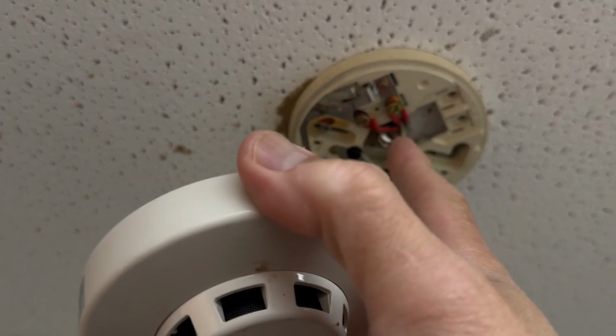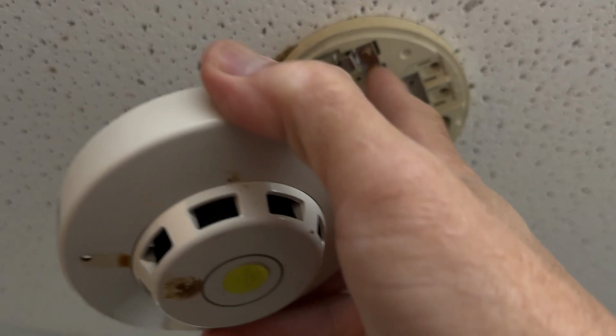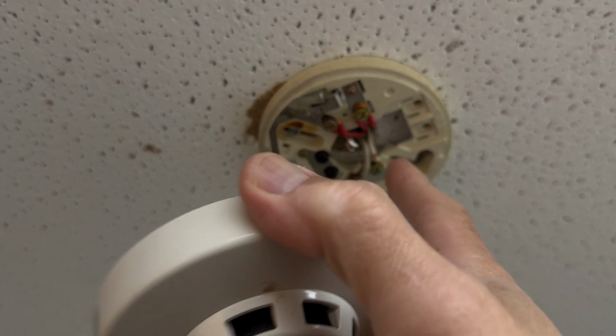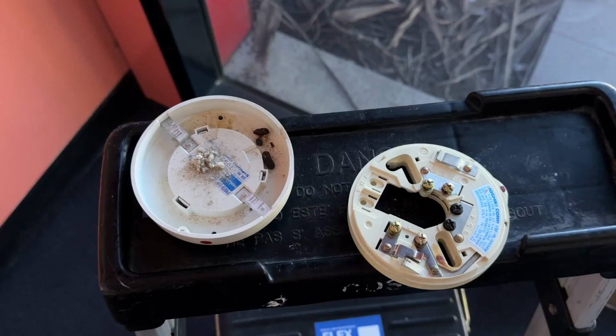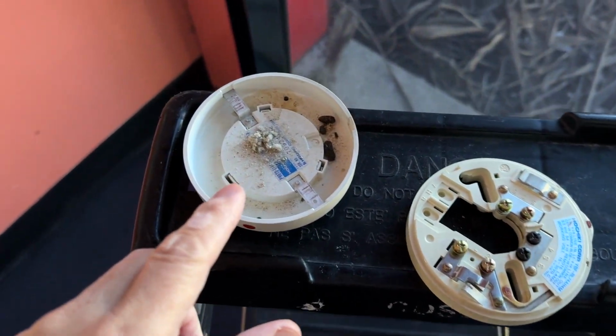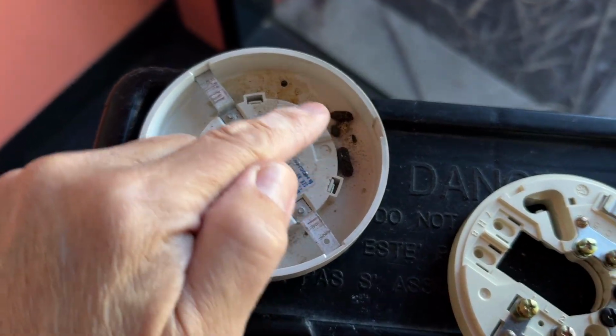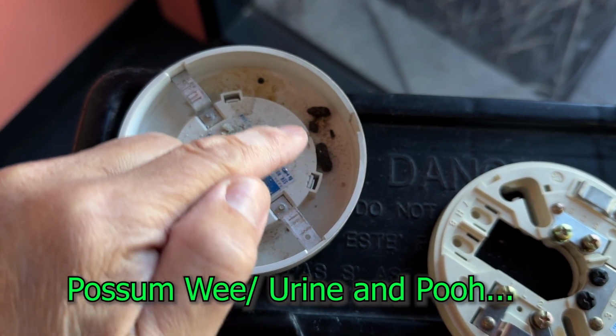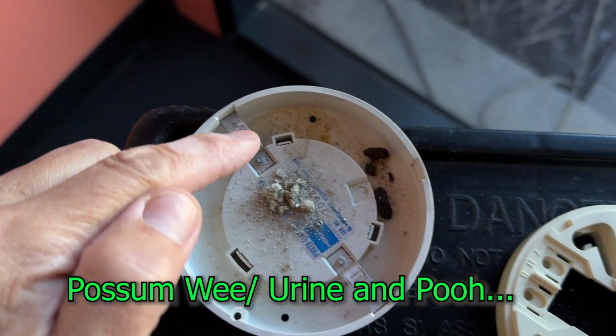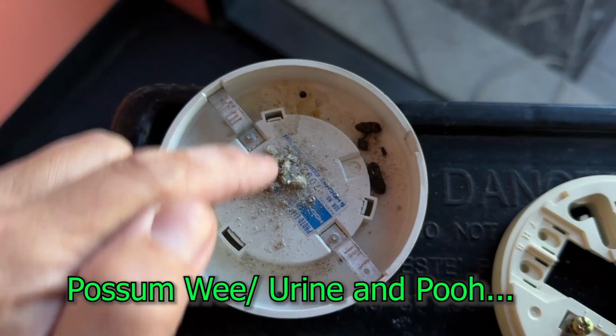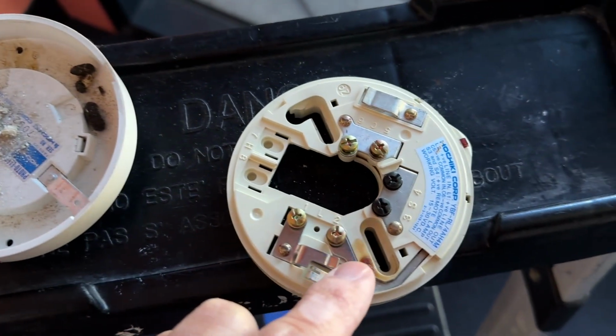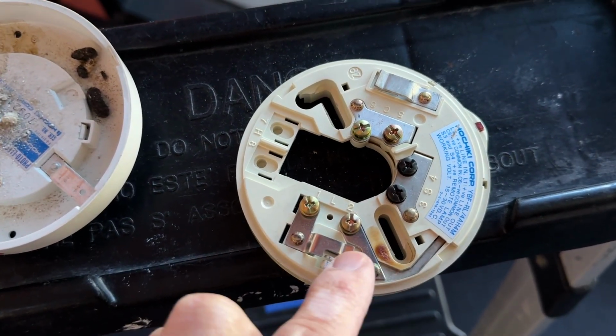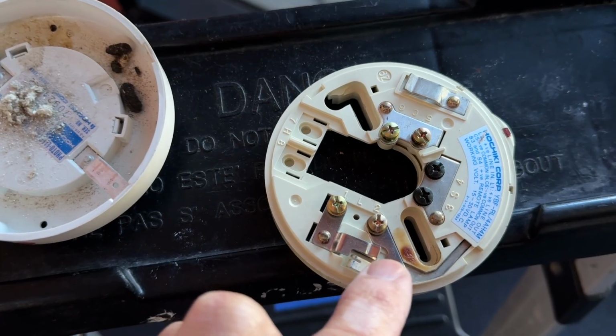We're going to remove this detector, and temporarily, since I don't have a spare, I will bridge it and then come back for that. So this is our removed detector. If you will see, there's some possum poo. Possum pee went inside the detector, and the base looks normal, but there are some traces of possum pee as well.